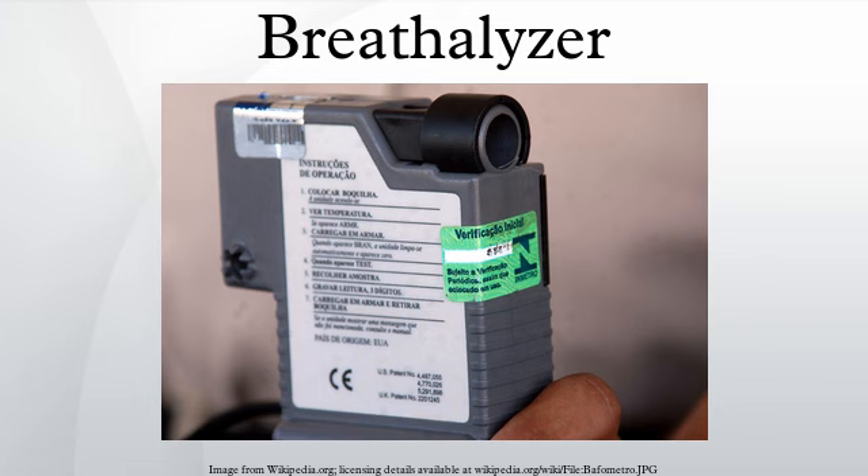Variance in how much one breathes out can also give false readings, usually low. This is due to biological variance in breath alcohol concentration as a function of the volume of air in the lungs — an example of a factor which interferes with the liquid-gas equilibrium assumed by the devices. Mixtures of volatile compounds can be more volatile than their components, which can create artificially high levels of ethanol vapors relative to the normal biological blood-breath alcohol equilibrium.